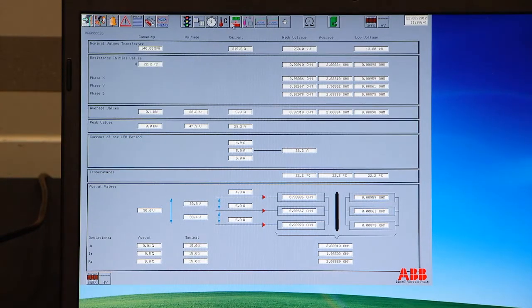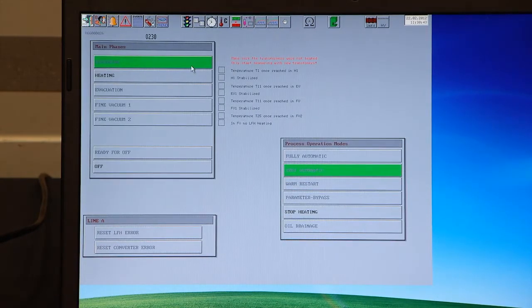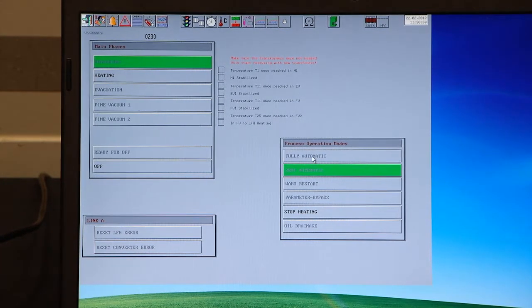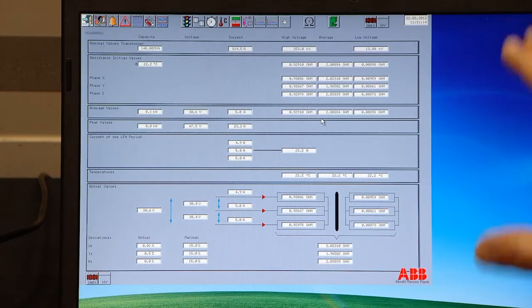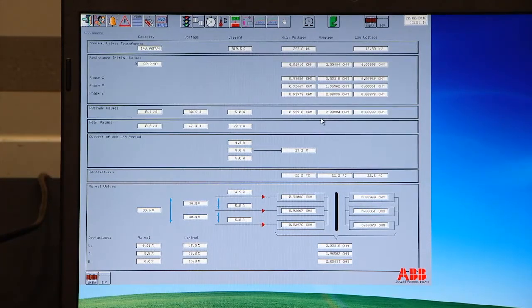Since we are in semi-automatic, he stopped here. Heating is green, is ready to start. It's black. If we would have had fully automatic, he would go automatically into that. And then when you match your resistance reading from the factory, you're doing it at 20 degrees in the factory. These values will be much higher when you do your 85 degrees resistance measurement. Right. So that you can calculate the difference and check the probability of it. With a conversion table. Make a conversion.